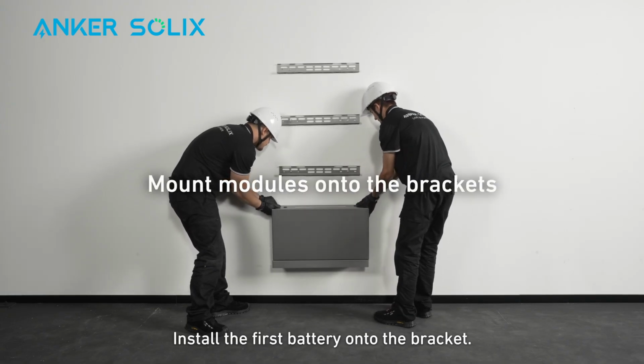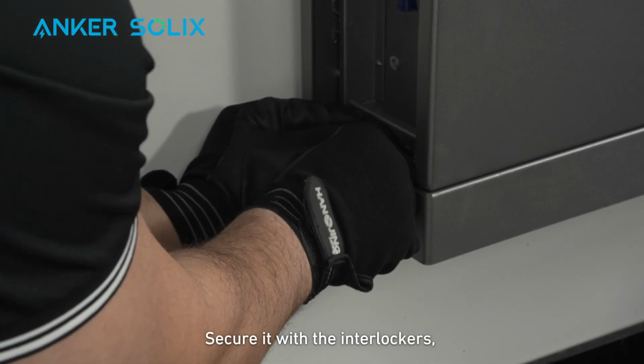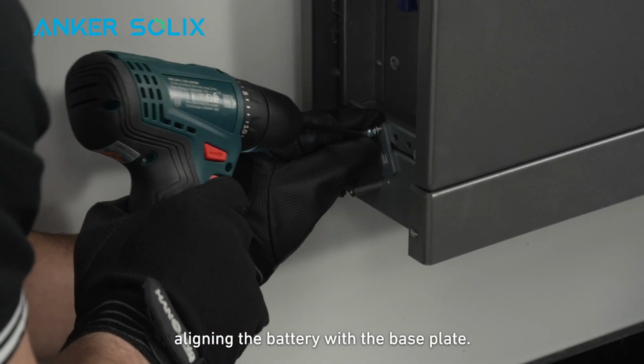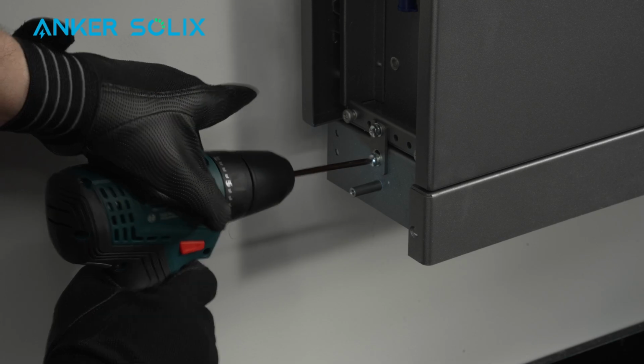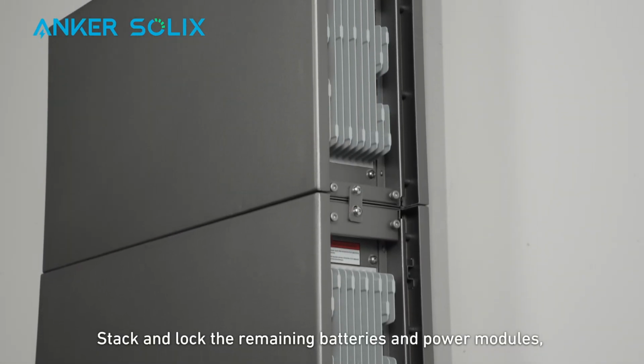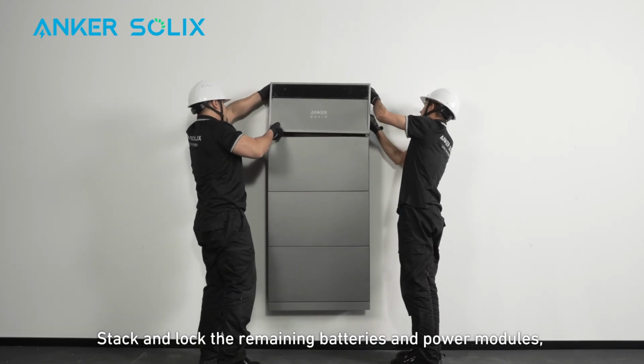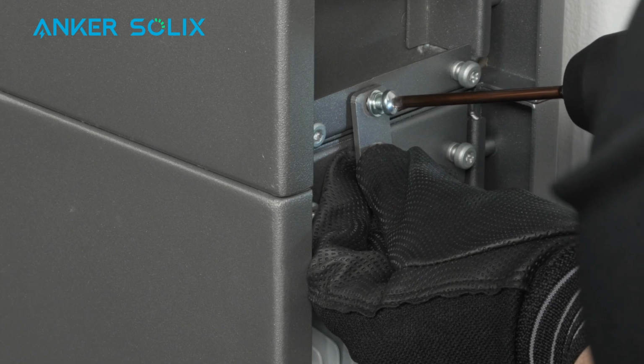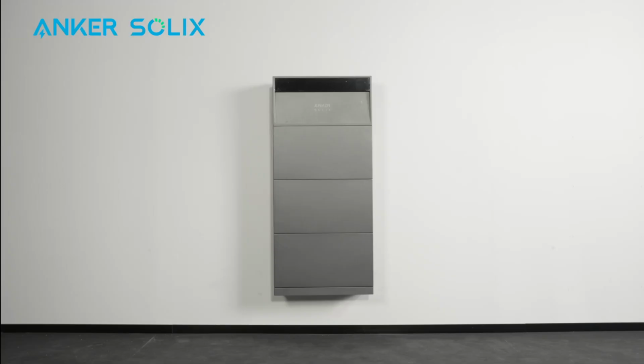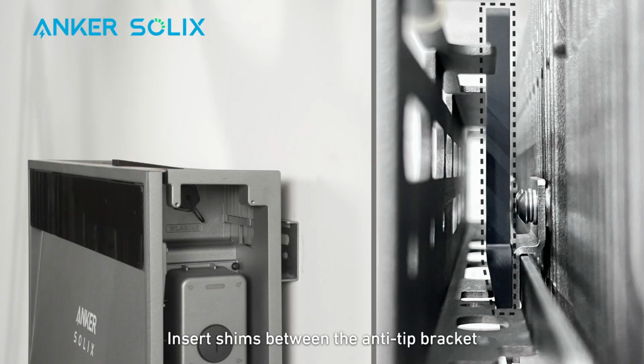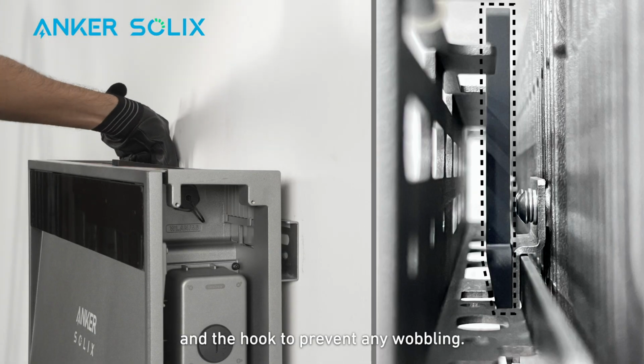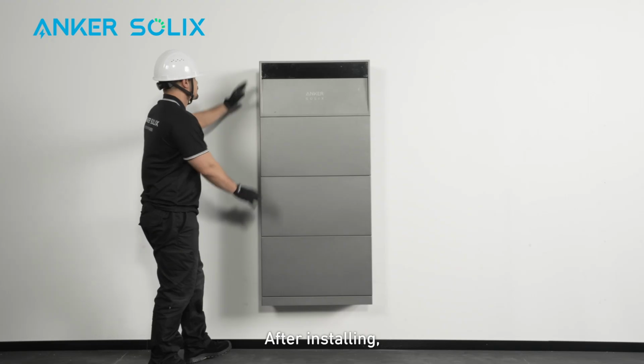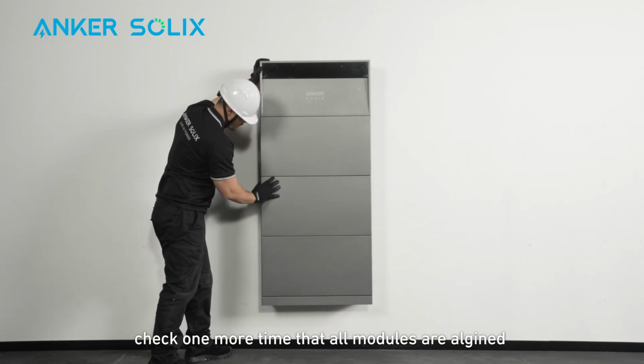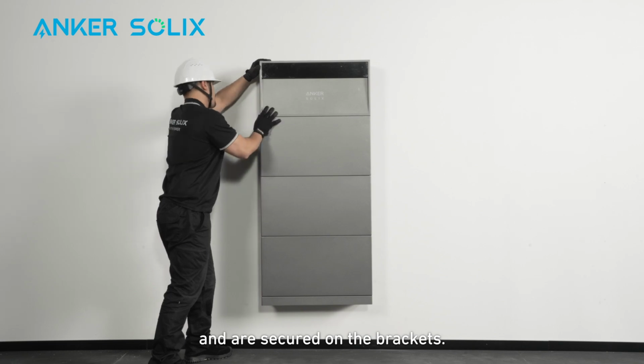Install the first battery onto the bracket. Secure it with the interlockers, aligning the battery with the base plate. Stack and lock the remaining batteries and power modules, then make sure they're aligned. Insert shims between the anti-tip bracket and the hook to prevent any wobbling. After installing, check one more time that all modules are aligned and are secured on the brackets.